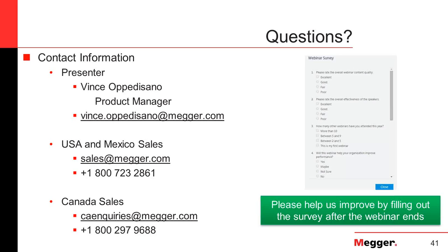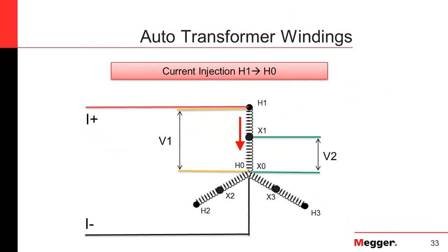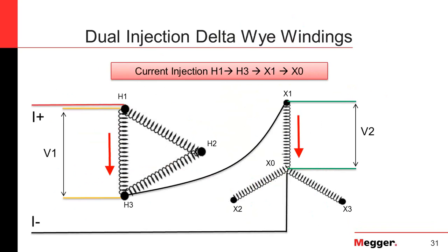Oh, actually, Thomas has clarified. He said a delta Y winding. Oh, yes, absolutely. In fact, if we look at a delta Y winding from some of what we had shown, you're going to test the two phases that are in the same direction. That is the goal. Those are the ones that are closest to the same direction. And so in this case, you're going to test here on the screen. You would see both of them going, and they're all flowing in the right way to saturate the core effectively.